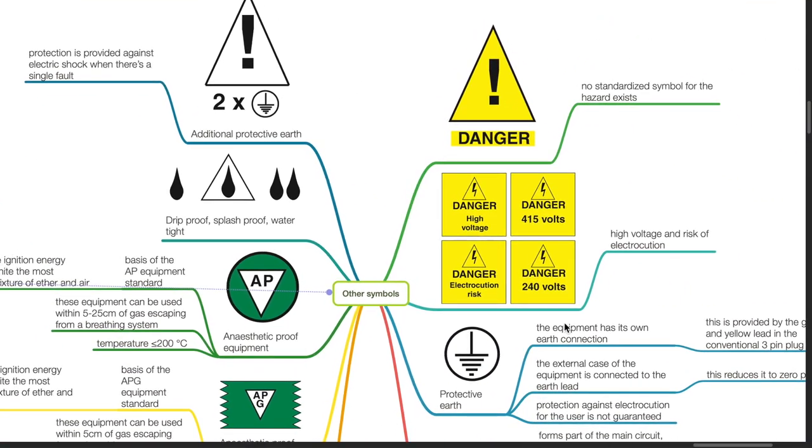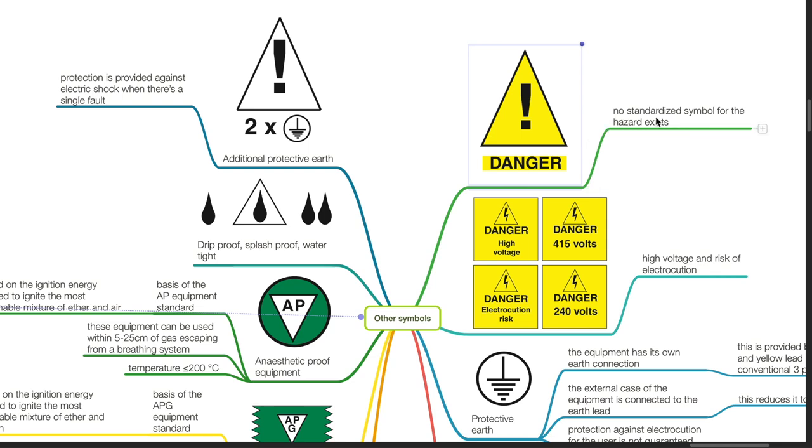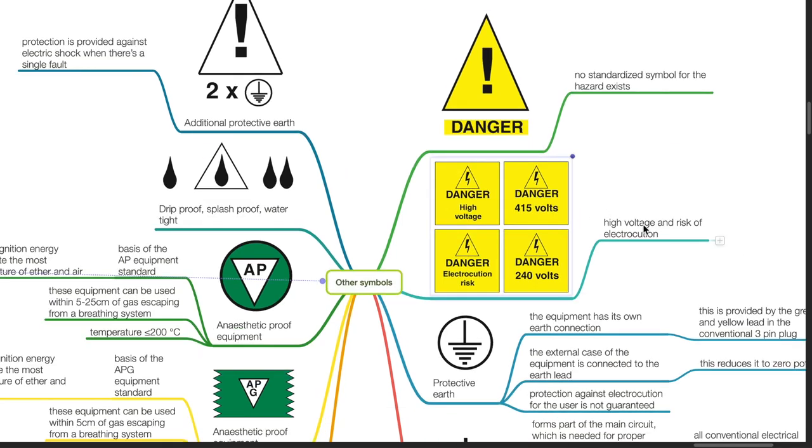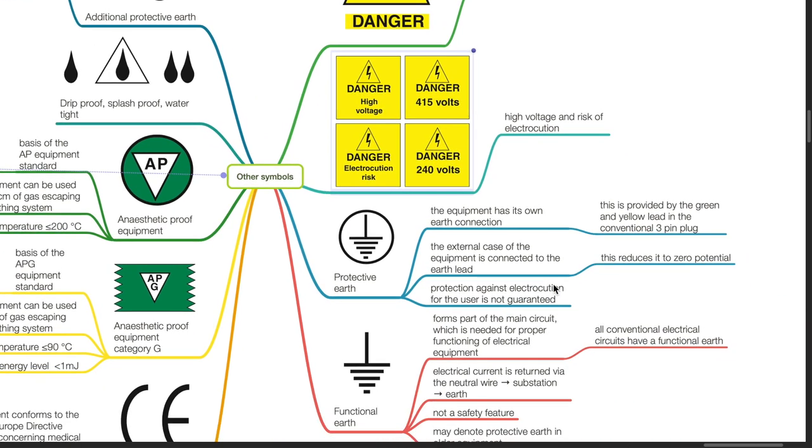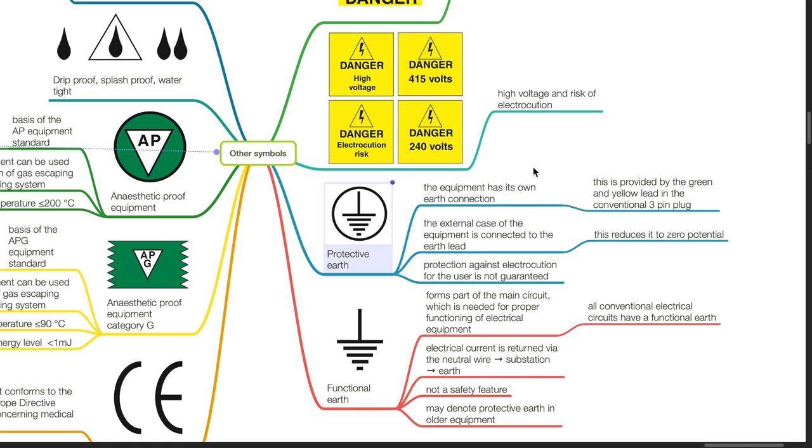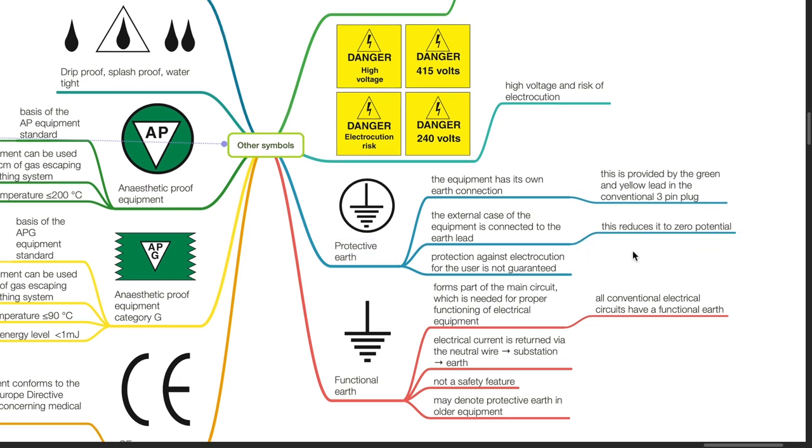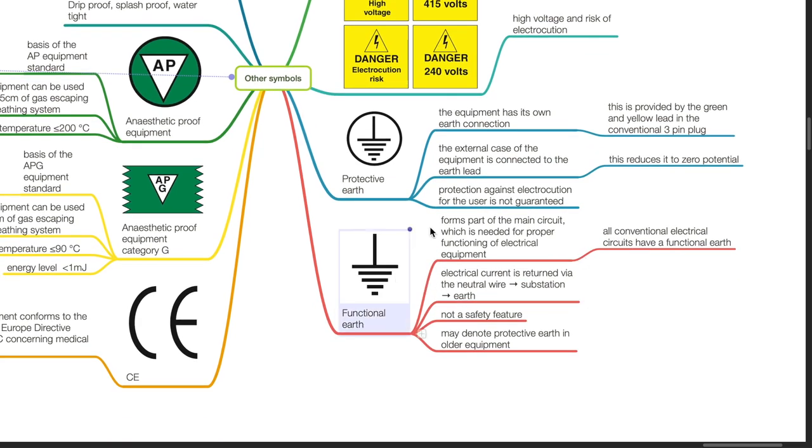These are other important symbols. The danger symbol has no standardized symbol for the hazard. High voltage and risk of electrocution symbol. The protective earth symbol indicates the equipment has its own earth connection, provided by the green and yellow lead in a conventional 3-pin plug. The external case is connected to the earth lead and reduces its potential to zero. Protection against electrocution for the user is not guaranteed. The functional earth symbol forms part of the main circuit needed for proper functioning of electrical equipment.